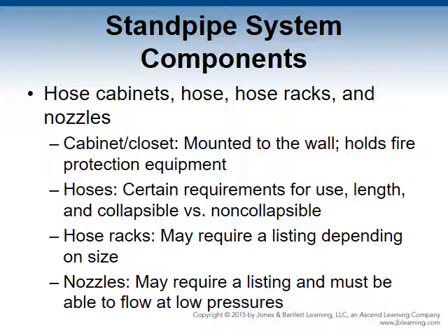Even though cabinets usually have glass doors, so the equipment is visible and accessible, they should be labeled. If cabinets are locked, they must have a breakable front, and a device that can be used to strike the glass must be accessible.